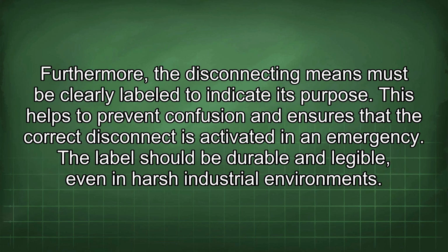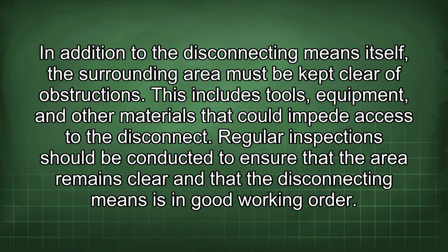Furthermore, the disconnecting means must be clearly labeled to indicate its purpose. This helps to prevent confusion and ensures that the correct disconnect is activated in an emergency. The label should be durable and legible, even in harsh industrial environments. In addition to the disconnecting means itself, the surrounding area must be kept clear of obstructions. This includes tools, equipment, and other materials that could impede access to the disconnect. Regular inspections should be conducted to ensure that the area remains clear and that the disconnecting means is in good working order.